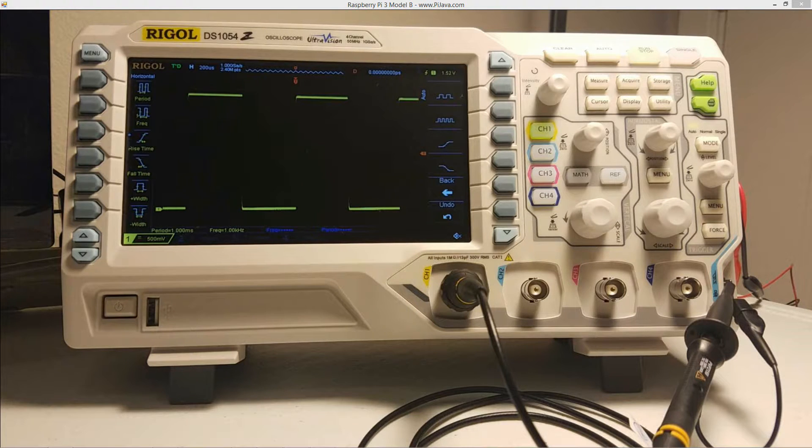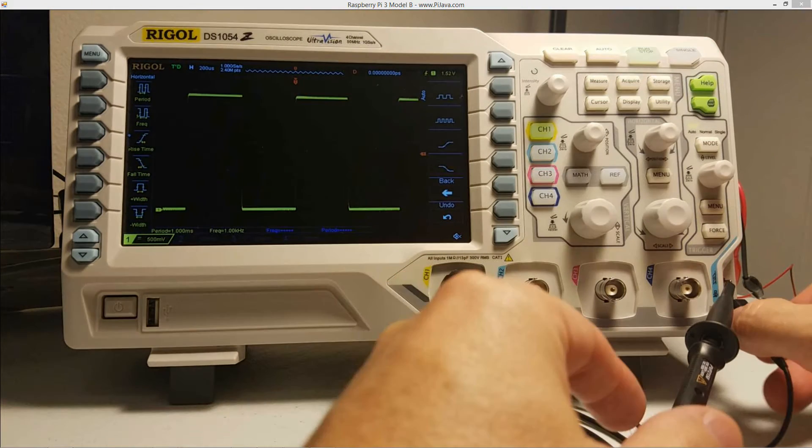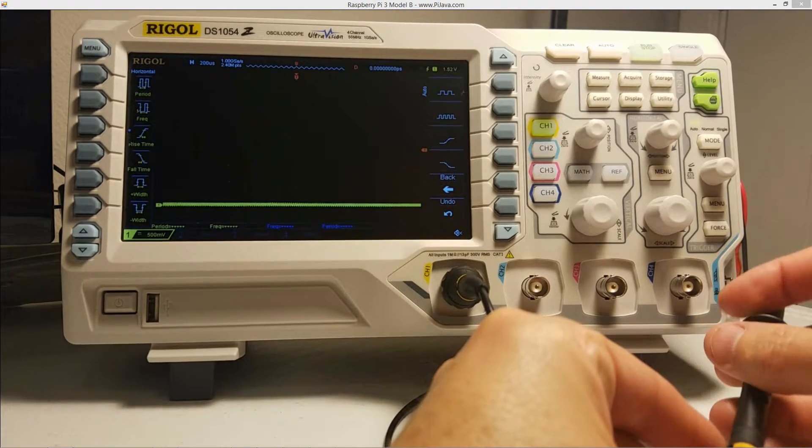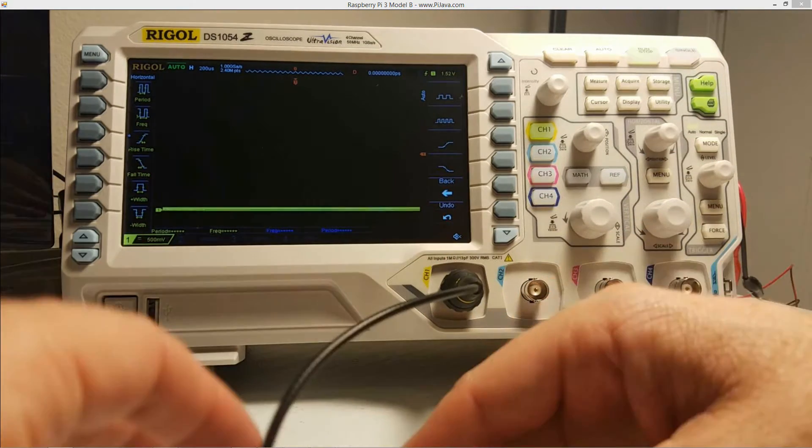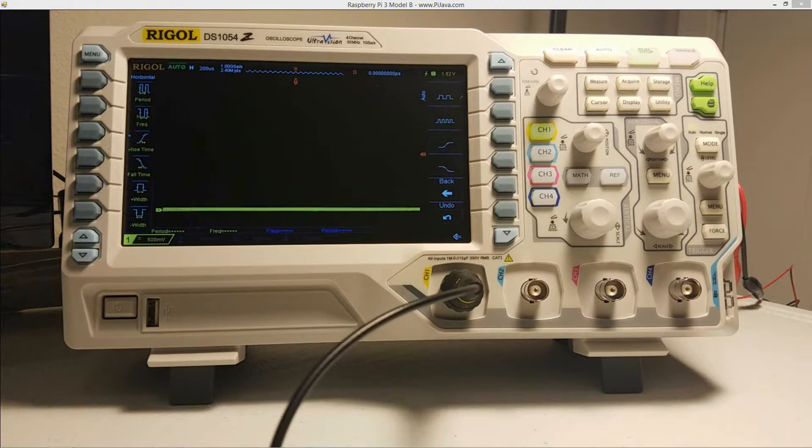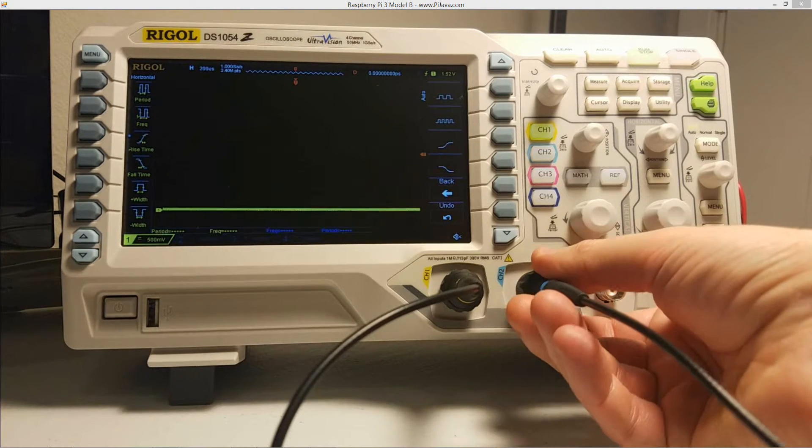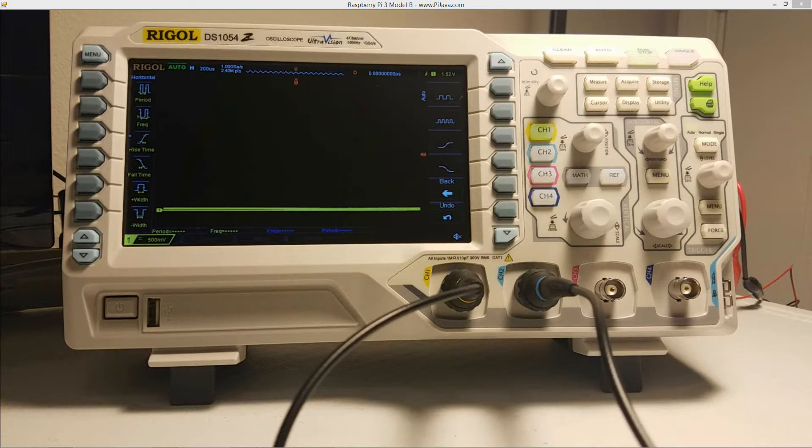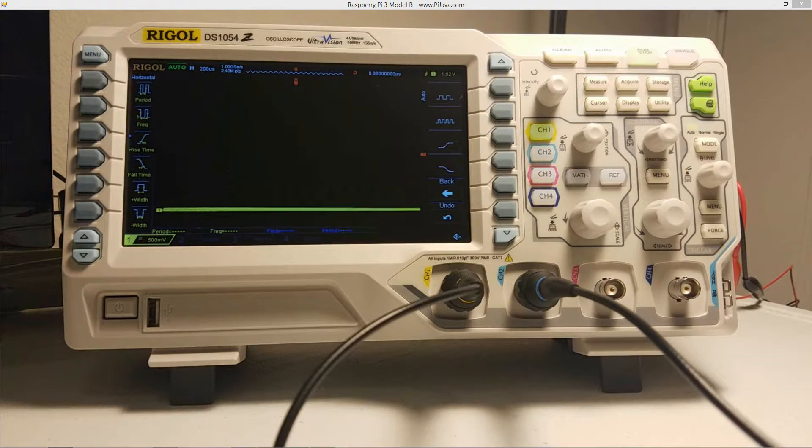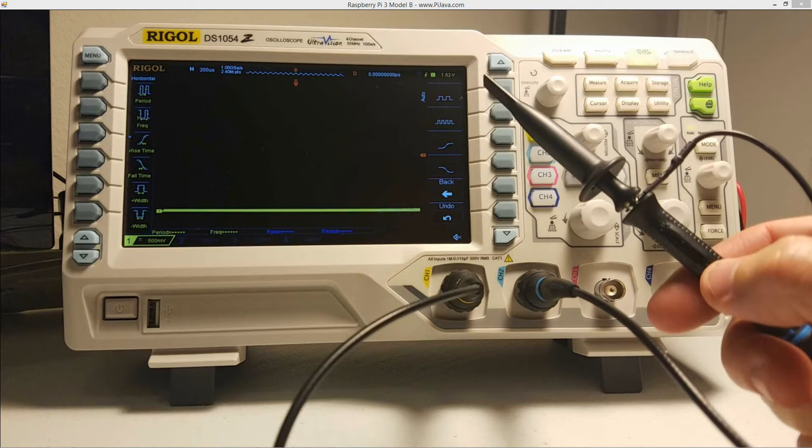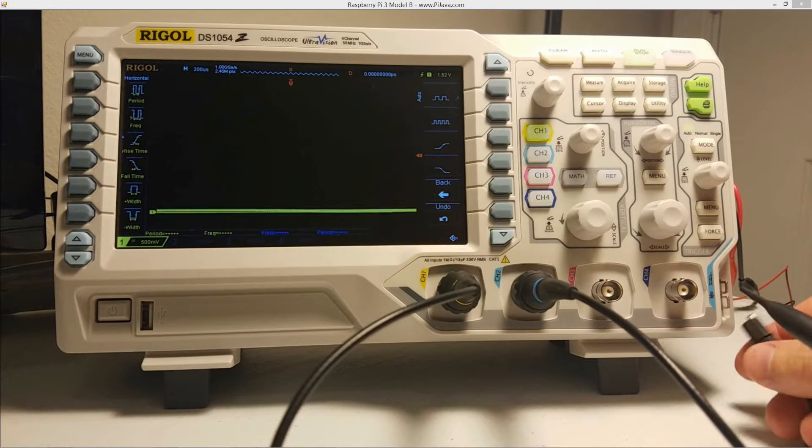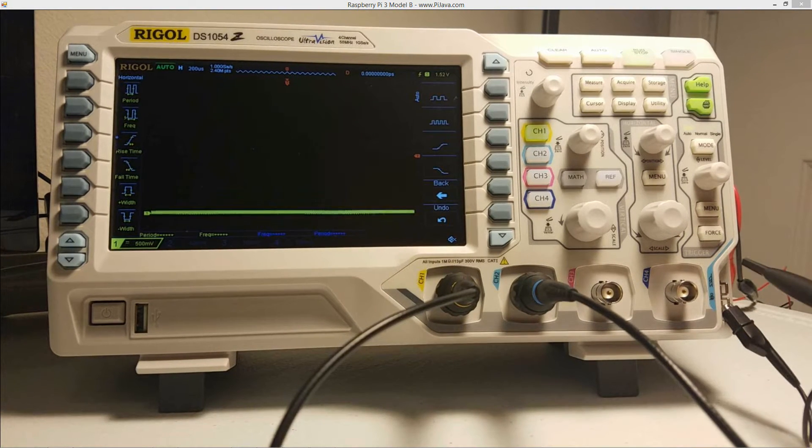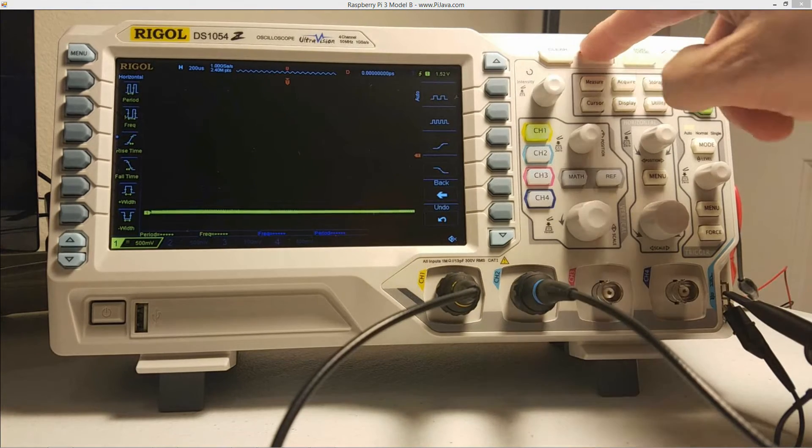And once we've got that set, then we're all done with this particular channel here. So we can just go ahead and unclip our earth ground there and unclip that one and set that one aside there. Now, it is recommended that each probe wire is compensated with each channel. In other words, don't take the blue probe wire and compensate it to channel one.